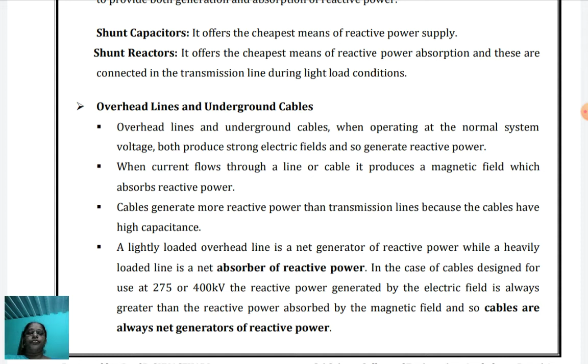Then the next component, overhead lines and underground cables. Both operate at the normal system voltage and both produce strong electric fields, so both generate reactive power. When current flows through the overhead line or underground cable, it produces a magnetic field which absorbs reactive power. The cable generates more reactive power than the transmission line because cables have high capacitance.